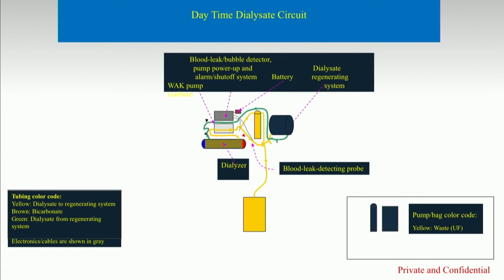We have data on that as well. So fresh dialysate goes into the dialyzer, and then the dirty dialysate goes into one cartridge, not three. It weighs much less, and this allows us to put all this not in 11 pounds, but in only 2 pounds.